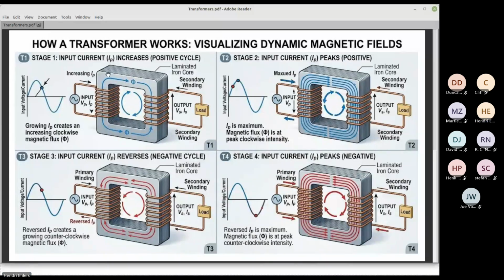Now, they have made a lot of different ways of constructing the core to try and insulate the plates from each other so that one will not complete a circuit. And that is typically where they use the EI core in order to insulate the plates from each other, so that they try and limit the amount of current that's flowing inside the core, because that will actually heat the core up, and that will cause obviously a loss, because you're converting energy to heat.